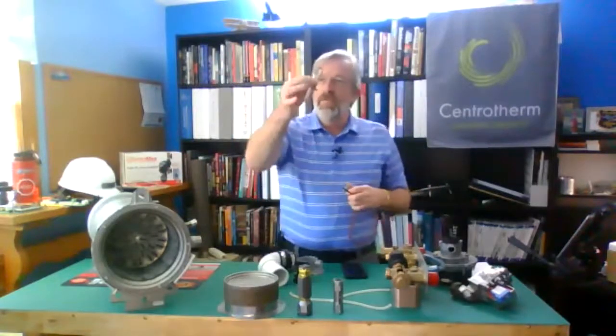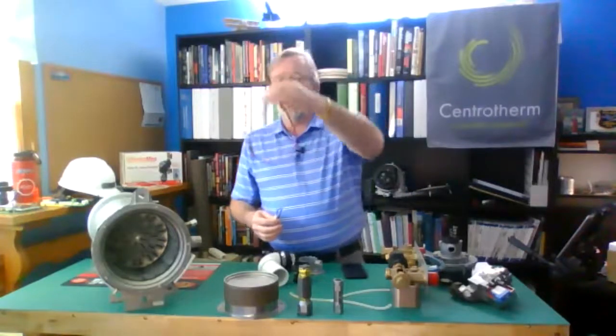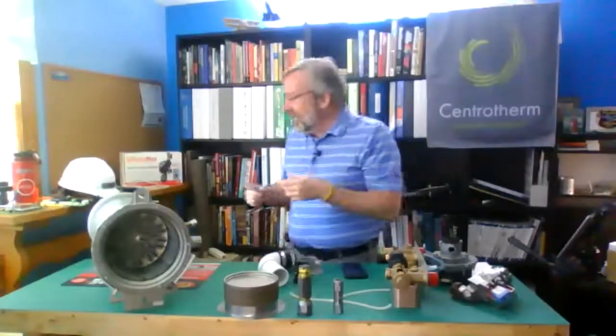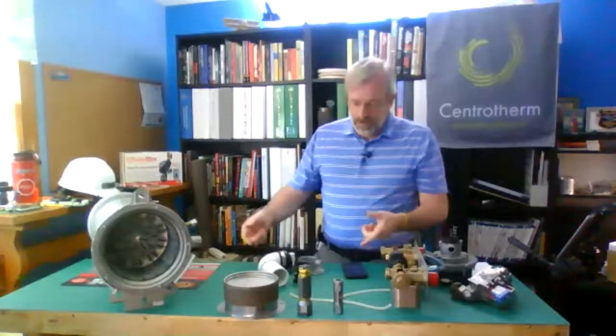But if I didn't get spark here, or I didn't get spark here, I definitely want to look at this cable, and I want to check for that. If it's an open circuit, it's going to be the same thing. And a lot of times that actually kind of creates a weak or intermittent ignition. And so one of the telltales of that could be some occasional flame failure ignitions. All right, so we've gone through that. Let's say all of that was good for us. What are we left to now?